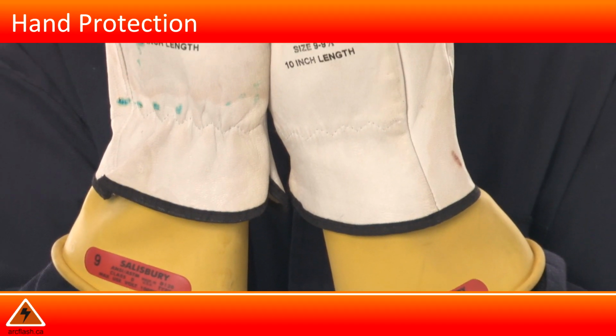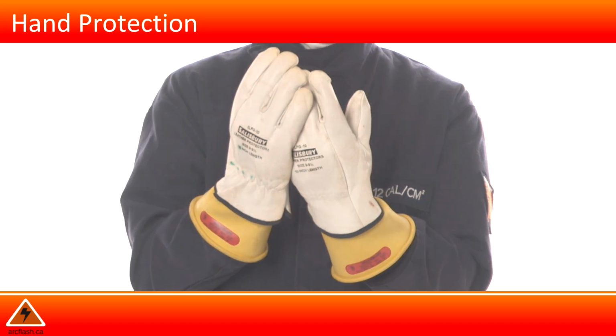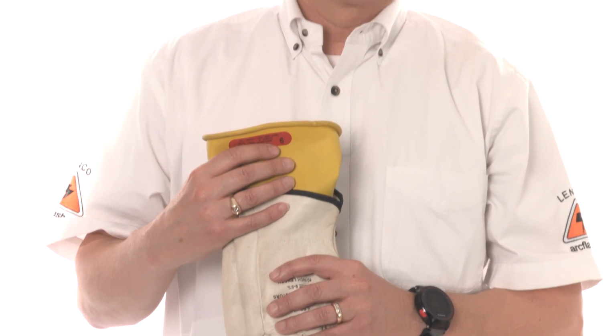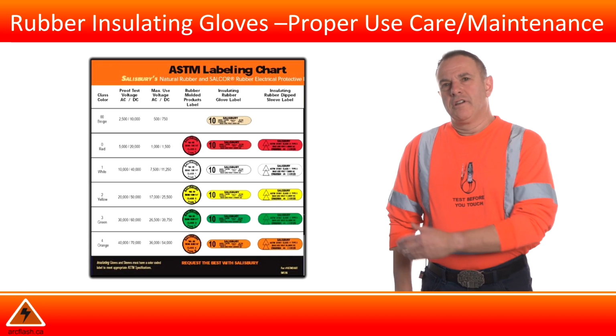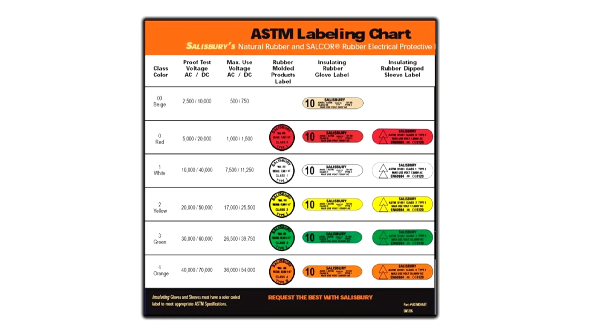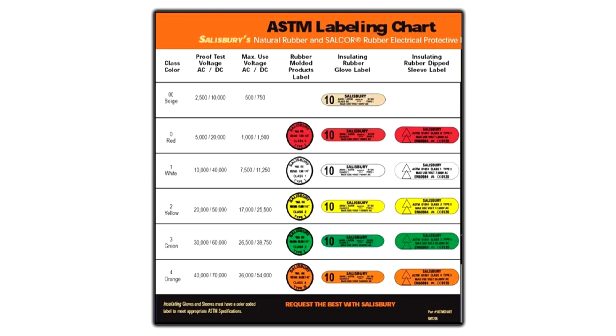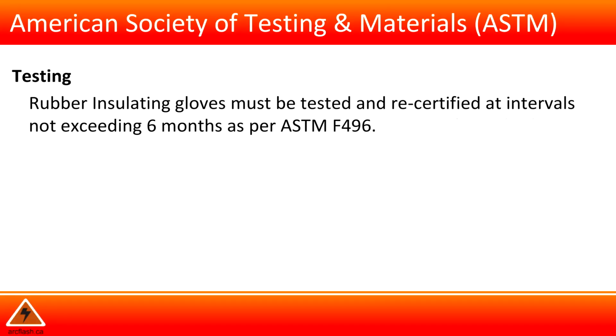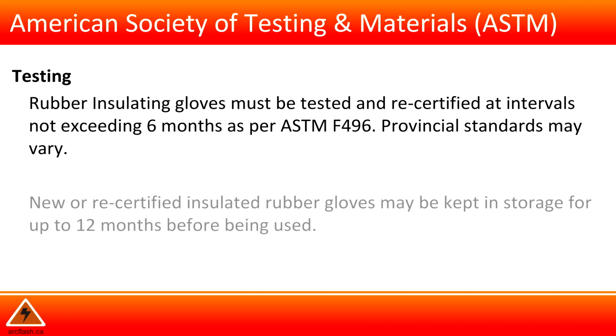Rubber insulating gloves with leather protectors protect a worker from electric shock. Also known as voltage-rated gloves, it is important to note the various classes of gloves. This chart illustrates the various glove classes and voltage ratings. Rubber insulating gloves with leather protectors must be tested before first issue and recertified at intervals not exceeding 6 months. This is as per ASTM F496. Provincial standards may vary. New or recertified rubber insulating gloves may be kept in storage for up to 12 months before being used again.